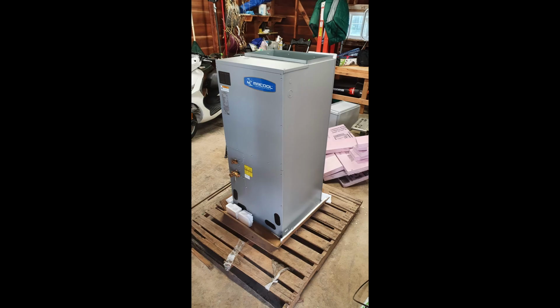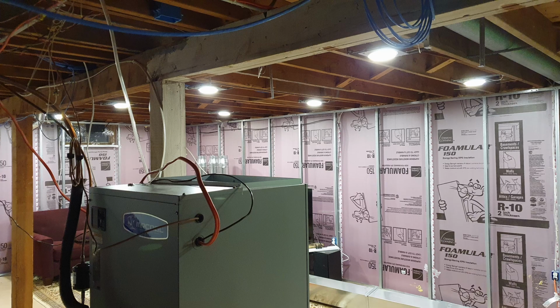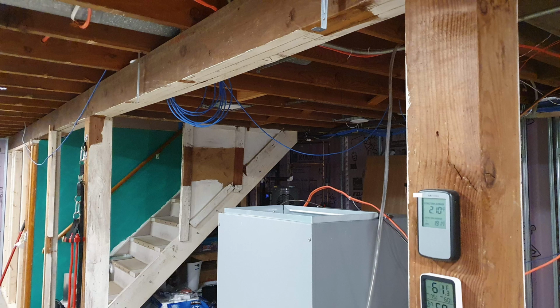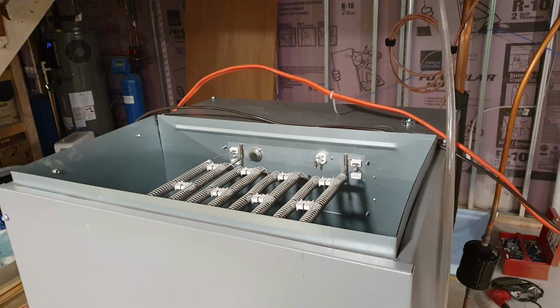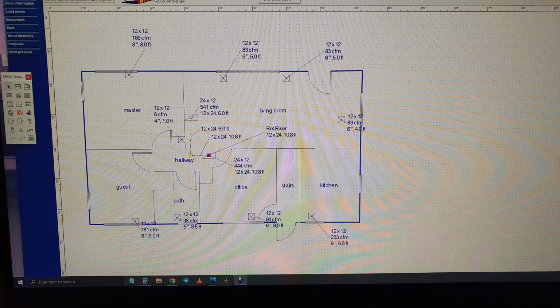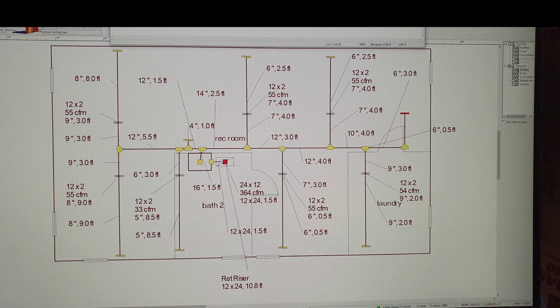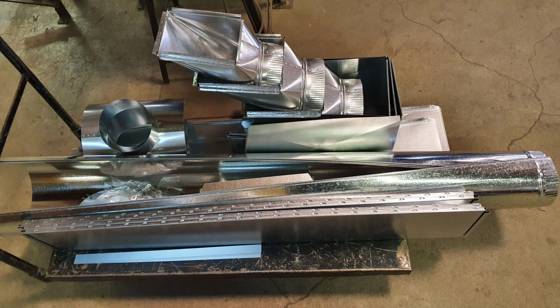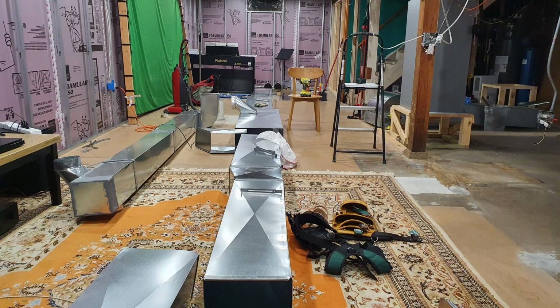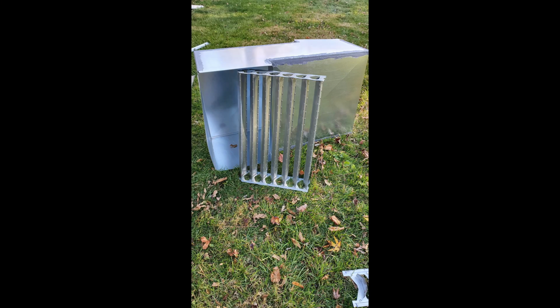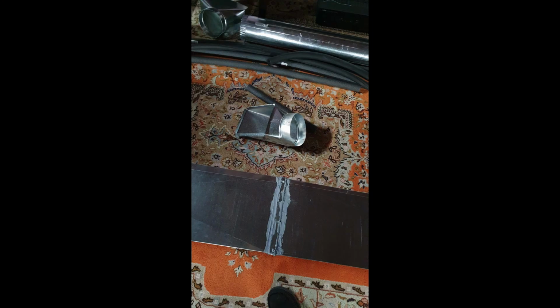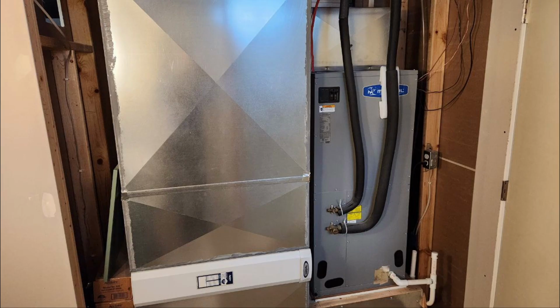So I opted for a cold climate heat pump. The heat pump we bought cost around $4,000 to $5,000, and at -5 degrees it can put out 24,000 BTUs, its full rated capacity. At -22 degrees Fahrenheit, it can put out 78% of its capacity. So it loses output capacity as temperatures get colder, but we still have electric resistance backup if we ever need it, so we're fine there.